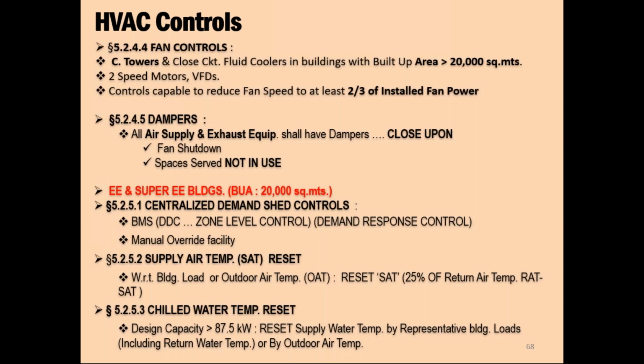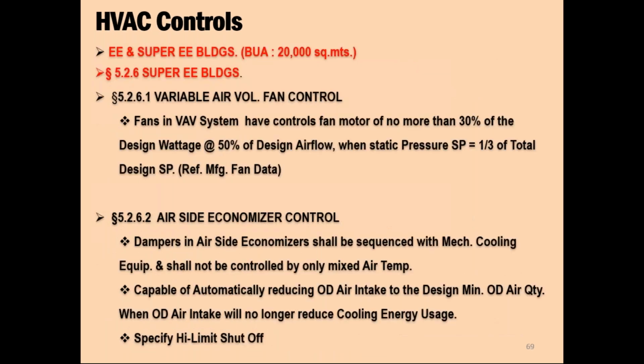each, kind of thing. So trying to save everything on the controls on the other side or user side, it could be much better to control your chilled water supply temperature first based on the feedback received, and then also it can be ramped up or down very easily if you have VFD in control.